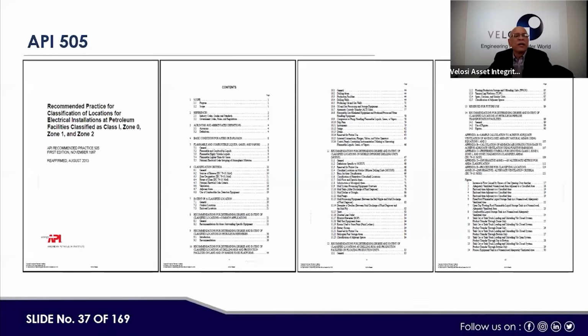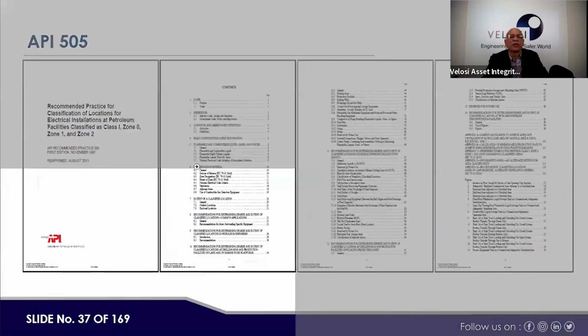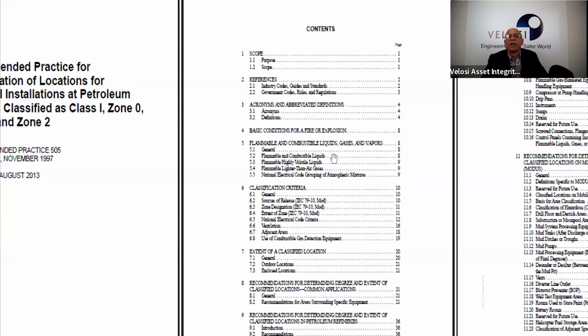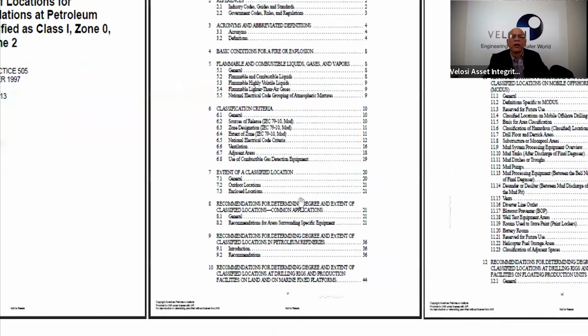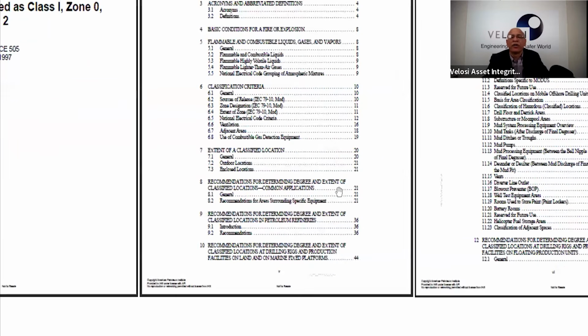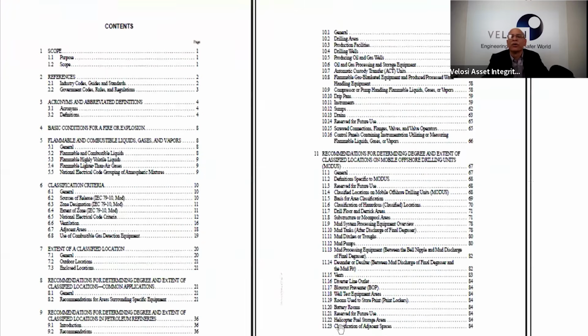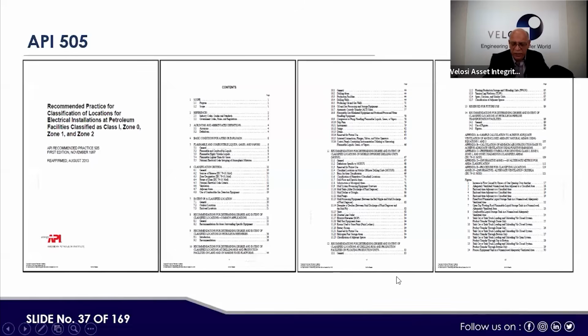Next one is API 505. This is a recommended practice for classification of locations for electrical installations at petroleum facilities classified as Zone 0, Zone 1 and Zone 2. And here the information is also similar. For example, flammable and combustible liquid, gases and vapors, then classification criteria, then extent of classification locations, and then recommendations for the determination of the degree of the extent of the classifications and so on. So these standards are self-explanatory and very easy to use if you wish to follow them.